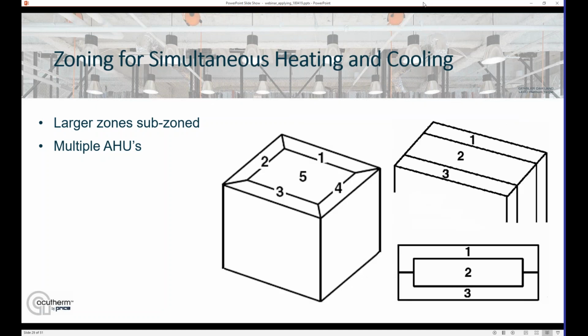It doesn't have to be the classic 5 zones. You can zone the building by face. You can, for example, take the entire southern face of a multi-story building and create a zone that way. Or if you've got a narrow rectangular building, you might drop it to 3 zones because you've got stairwells in the ends or other spaces that aren't as critical and allow you to reduce the number of air handlers that way.